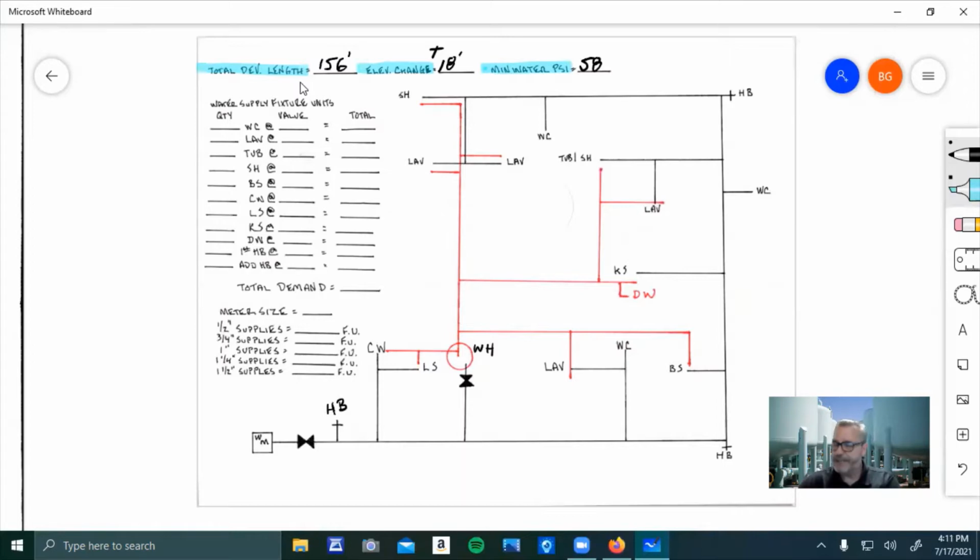So as the pipe rises, you're lowering your pressure. So in 18 feet, you have a pressure loss every foot of 0.43 psi. Chapter 6 doesn't talk about 0.43 psi. What they want is 0.5 psi. And this is all based on chapter 6, okay?